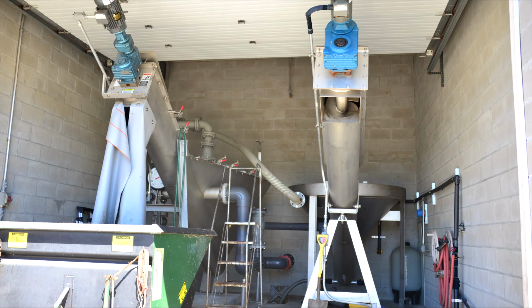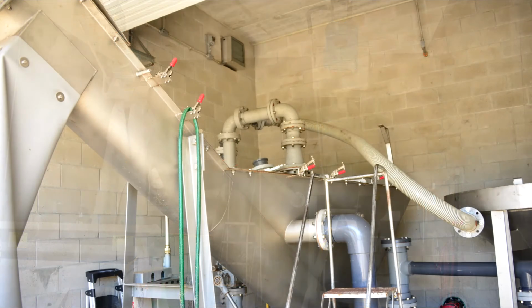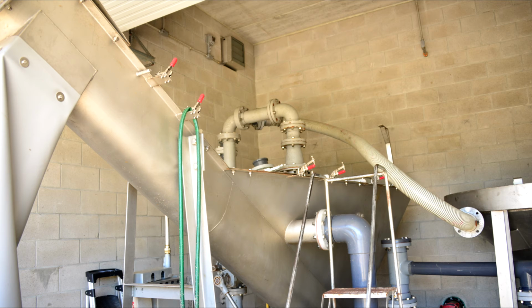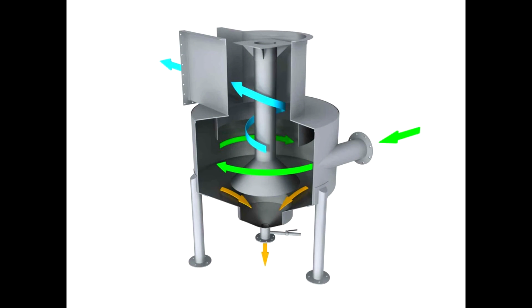The Grit King consists of a hollow, cylindrical vessel with a sloping base and a flat top. Flow follows a predetermined path through the vessel, causing the contents to rotate slowly about the vertical axis, forming a small circle within a large circle. Flow spirals down the perimeter, allowing the grit and sand particles to settle out by gravity.